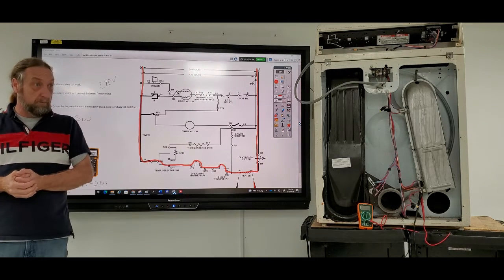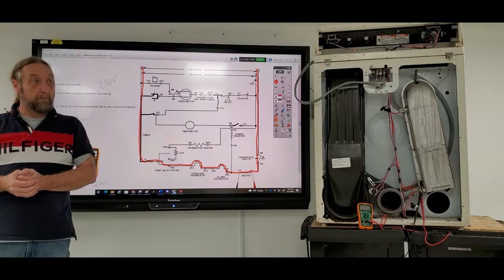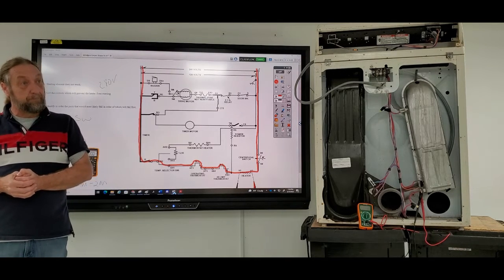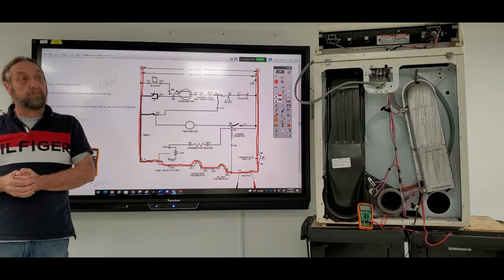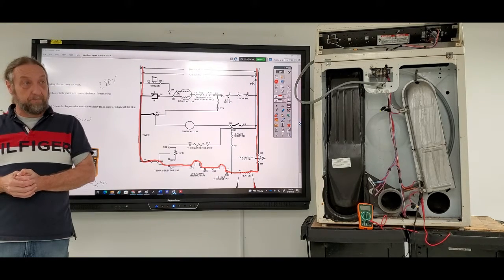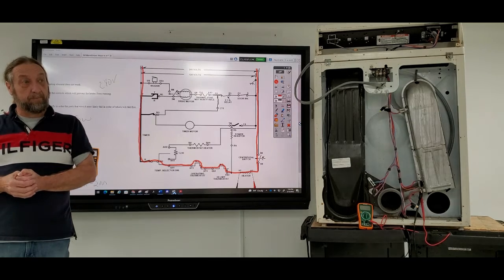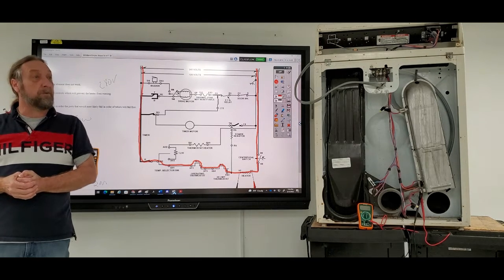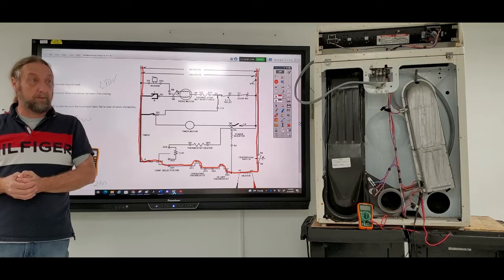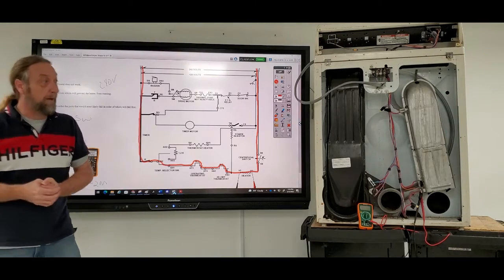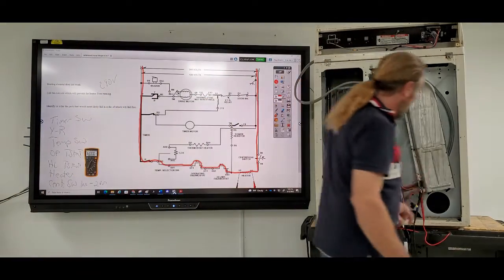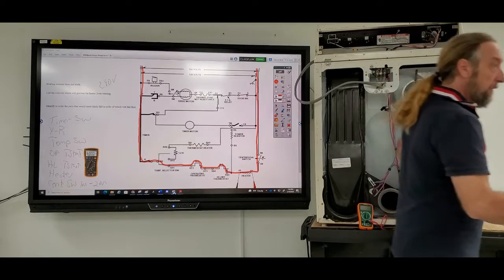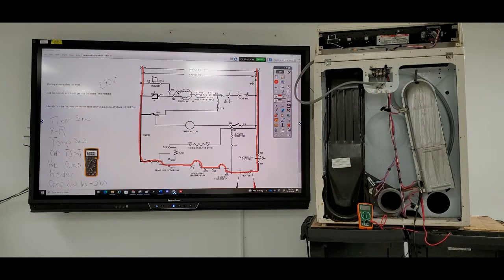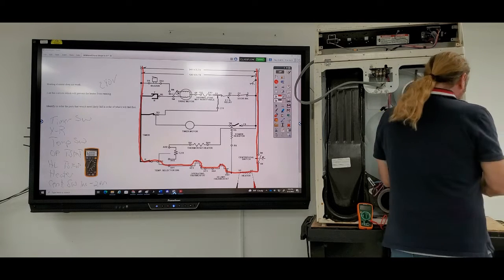Okay, well, I've had those heaters sag, hit neutral, or hit the casing, and then I end up with a heater that's supposed to produce 2,000 watts worth of power, or heat, producing like 750, because it cut short. That's technically a short circuit. It's a ground. It's not a short circuit. It's a grounded heater. Well, we've had on these heaters here, the disassembly is crazy. On this heater here was very common if a customer had poor airflow.